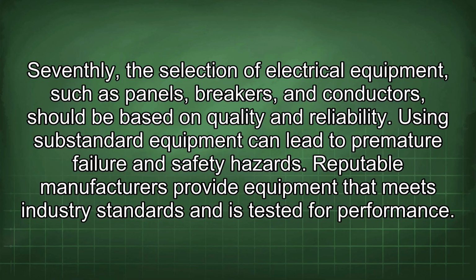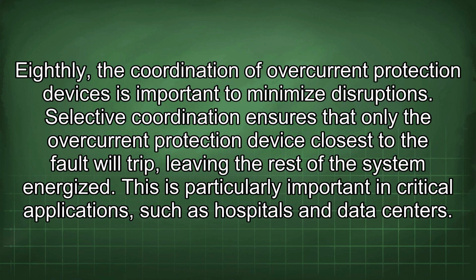Seventhly, the selection of electrical equipment, such as panels, breakers, and conductors, should be based on quality and reliability. Using substandard equipment can lead to premature failure and safety hazards. Reputable manufacturers provide equipment that meets industry standards and is tested for performance. Eighthly, the coordination of overcurrent protection devices is important to minimize disruptions. Selective coordination ensures that only the overcurrent protection device closest to the fault will trip, leaving the rest of the system energized. This is particularly important in critical applications such as hospitals and data centers.